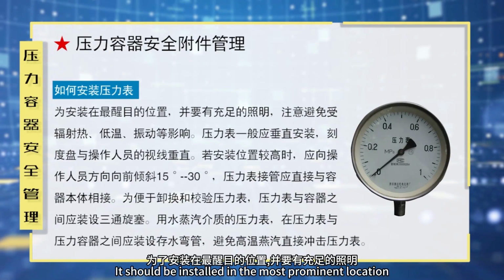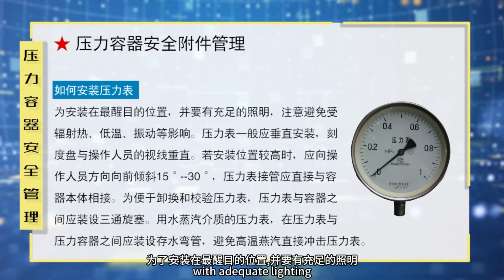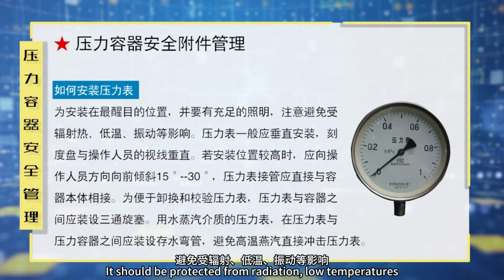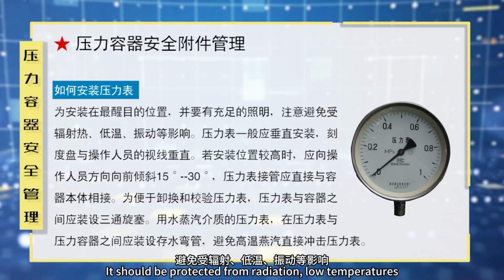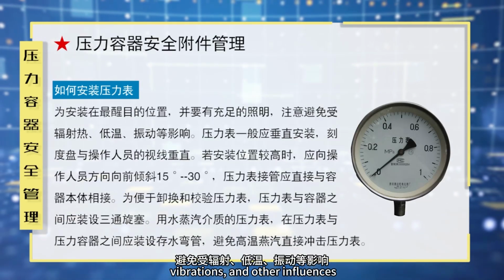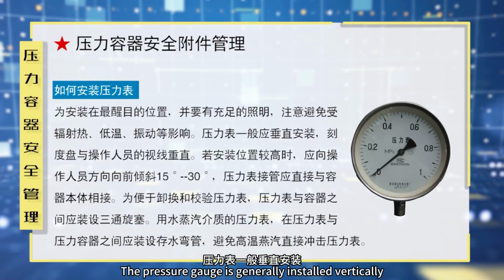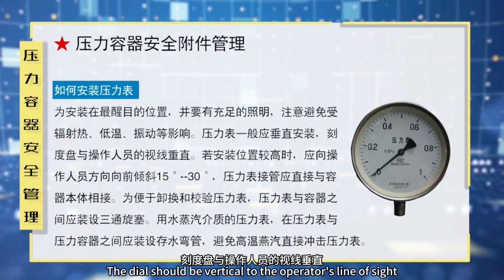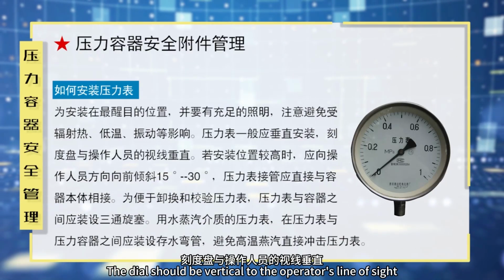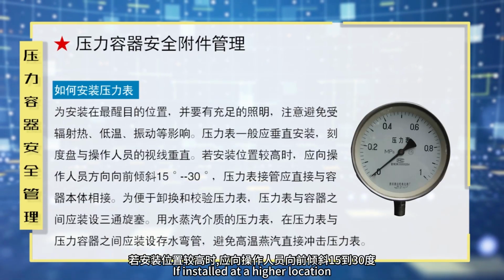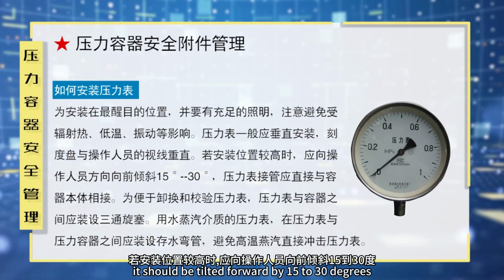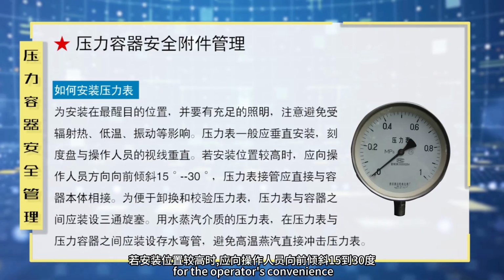How should the pressure gauge be installed? It should be installed in the most prominent location with adequate lighting. It should be protected from radiation, low temperatures, vibrations, and other influences. The pressure gauge is generally installed vertically. The dial should be vertical to the operator's line of sight. If installed at a higher location, it should be tilted forward by 15 to 30 degrees for the operator's convenience.